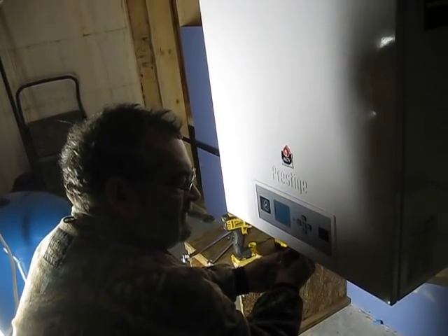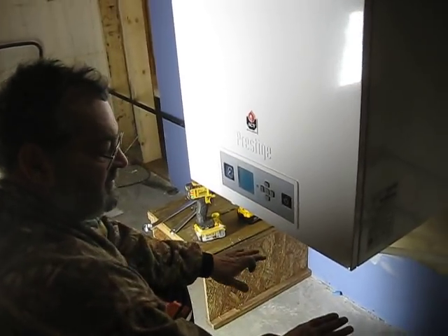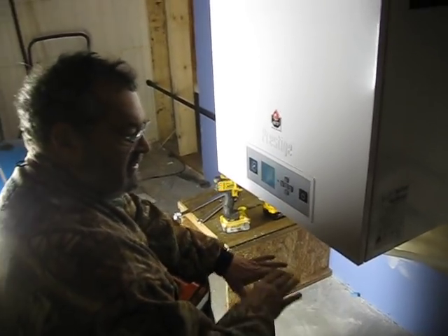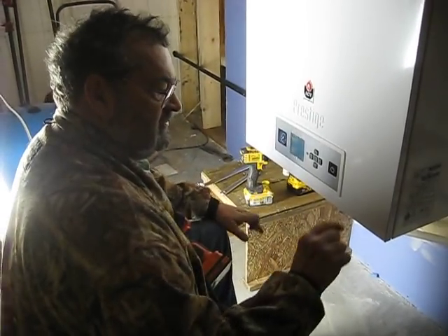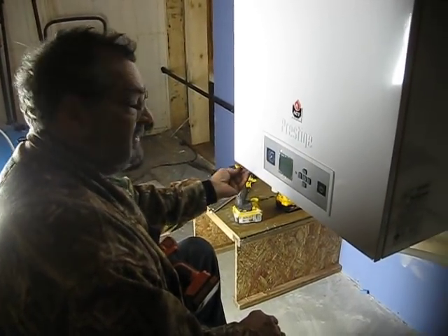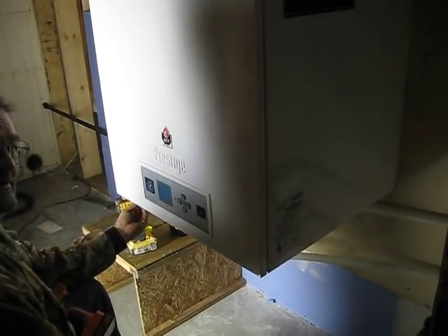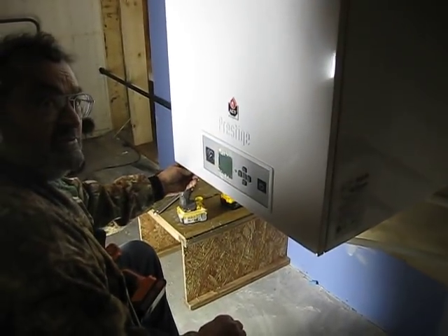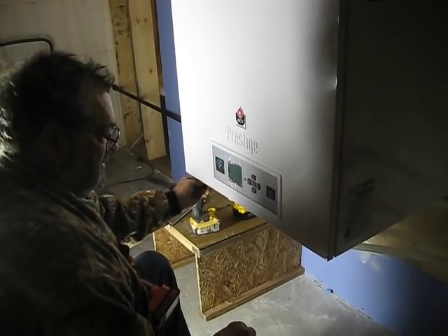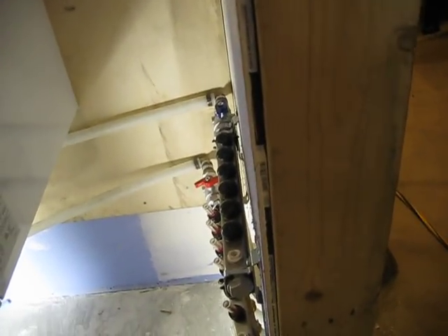There's a retrofit. There's three ways to put in in-floor heat. One is in the concrete, the other is in gypcrete, and then the other, they've got a system of 5/8-inch stuff where they lay the pipe to do retrofits in older houses. And then a fourth way is through these rafters, but that's a real poor and expensive way to do it, like in the floors of an old house. Oh, right. You can run them that way. But your most efficient way is to heat this big giant slab of concrete toasty. Yep. Can't wait. Yeah, well, you're pretty close.